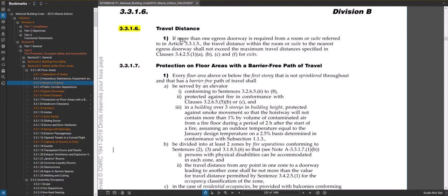Going to the travel distance section under location of exits, you need to ensure you're not exceeding the maximum distances listed. Read through your specific use and whether the building is sprinklered or not to find the applicable maximum. Article 3.3.1.6 states that if you have more than one egress doorway, the travel distance within the room or suite to one of the egress doorways shall not exceed those travel distances. If you only have one egress doorway, that limitation is already built into the single-door requirements.